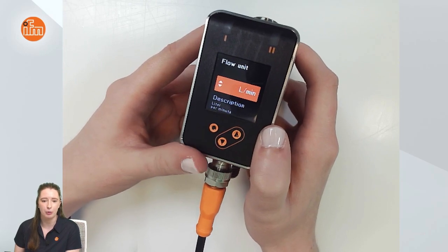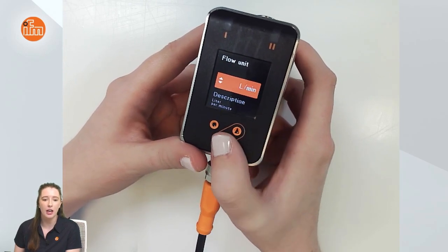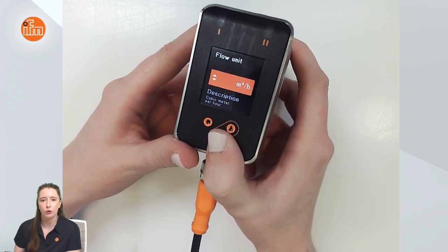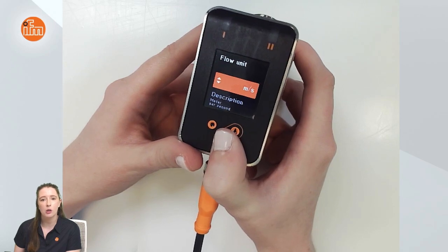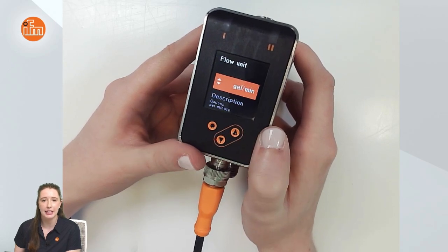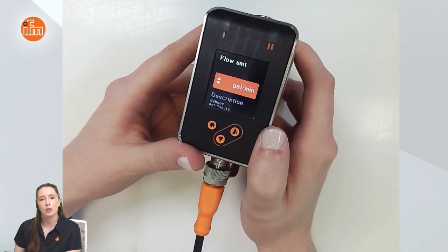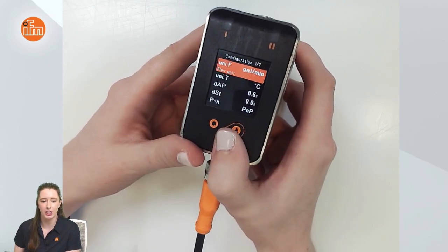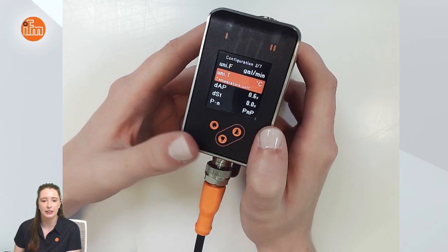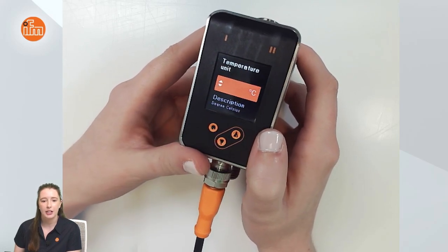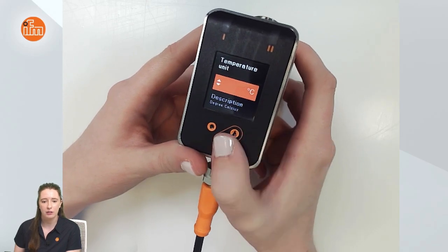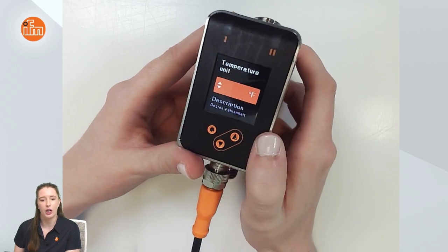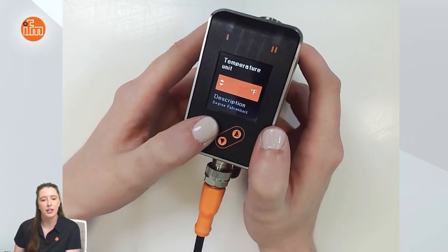Here you can see it is set for liters per minute. If you hold down either the up or down arrow key, you'll see the bar load and then you're able to toggle through your different options. In this video I'm going to change it from liters per minute to gallons per minute. Once you're at the parameter you want to set, you press enter and then you're back in the configuration menu. I'll then go down to uni.t and press enter to change it from Celsius to Fahrenheit by holding down either the up or down arrow key, letting the bar load, and toggling through your options. Once you're on Fahrenheit you can press enter.